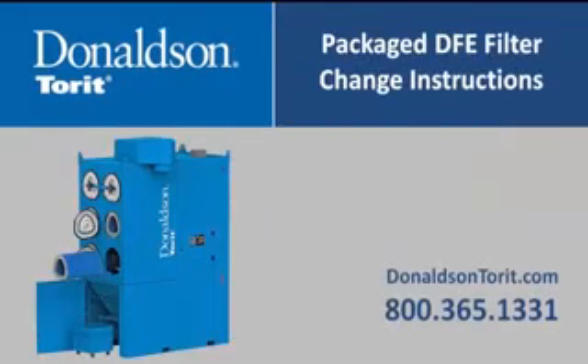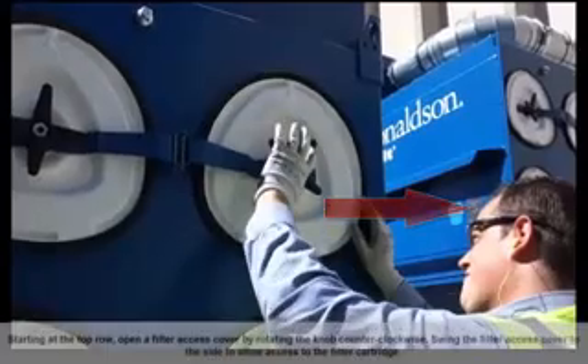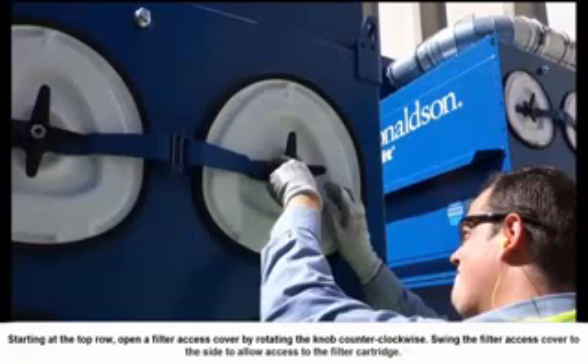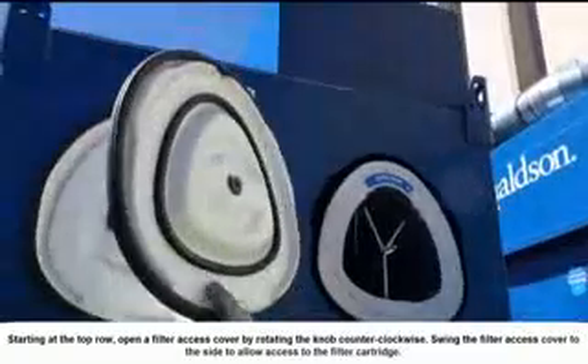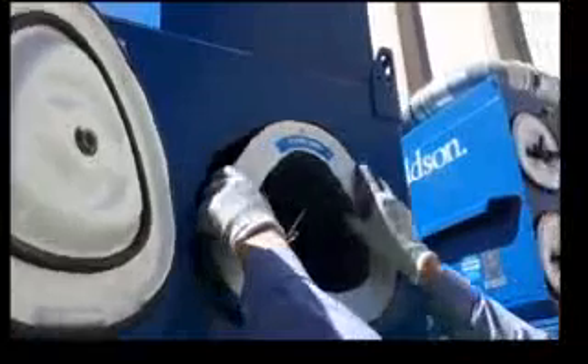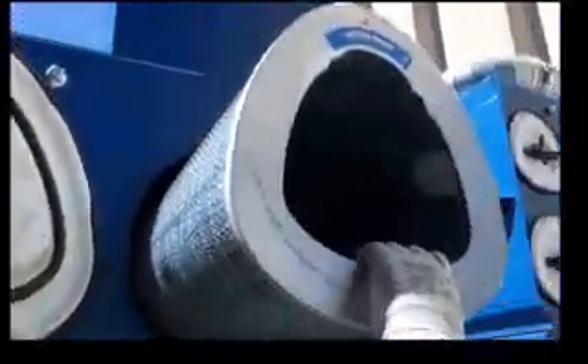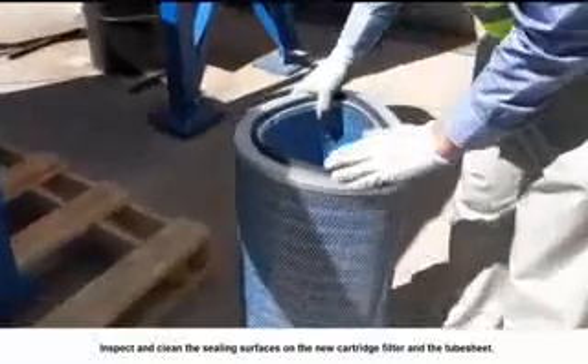The following section covers instructions for changing out a filter cartridge on the Packaged DFE. To begin, turn off the collector and lock out all energy sources. Starting at the top row, open a filter access cover by rotating the knob counter-clockwise and swing it to the side. Slide the exposed filter cartridge out of the access port along the suspension yoke, then remove and dispose of it properly.